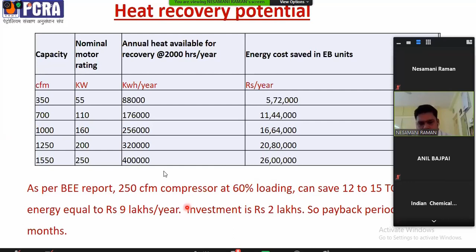The company is Lupin Pharma. What they did is they have a two-stage compressor, and they implemented this heat recovery system. After the first stage, soft water at ambient temperature goes through a heat exchanger and extracts the heat. Then it goes to the second stage exit and again extracts the heat, and through a common header, both stage waters combine and go to the boiler as feed water.